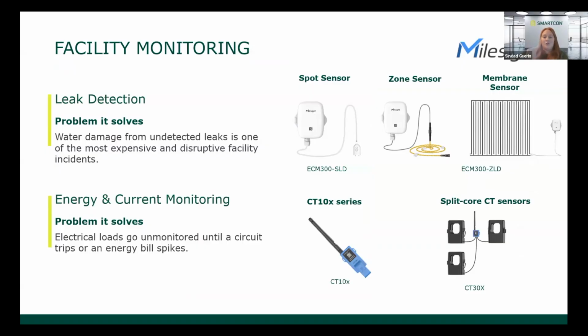There are four different types of leak sensors. Here you'll see three: the spot sensor, the zone sensor, and the membrane sensor. The spot sensor has a probe and is good under large pieces of equipment like domestic hot water systems, laundry, or kitchens, anywhere water may pool. The zone sensor is a rope sensor, so that yellow line extends.